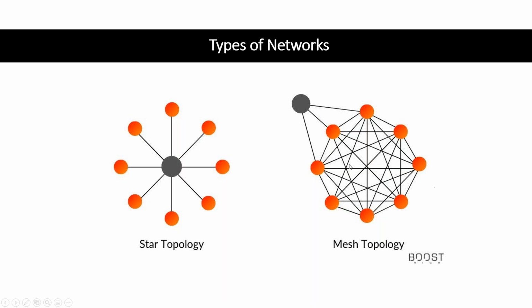With a mesh design, you have multiple connections to the source through multiple passageways. So you can actually use other points on the network to pass through and get your access to the main hub. And the benefit of this is it gives you a level of redundancy of signal. It gives you a level of healing. So if there is a device that goes down in the system, everything keeps running, everything keeps reporting. It just has multiple pathways to get back. So it's just an excellent overall design while we're looking at these systems.